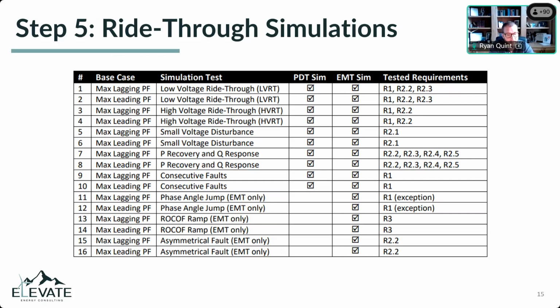These look at reactive and active power recovery and responses, and consecutive fault tests. We've also got additional tests focused only on the EMT space, because results in the phasor domain aren't sufficient or phasor domain tools can't represent things like phase angle jump, rocof, and unbalanced fault tests - those we really focus on only in EMT.